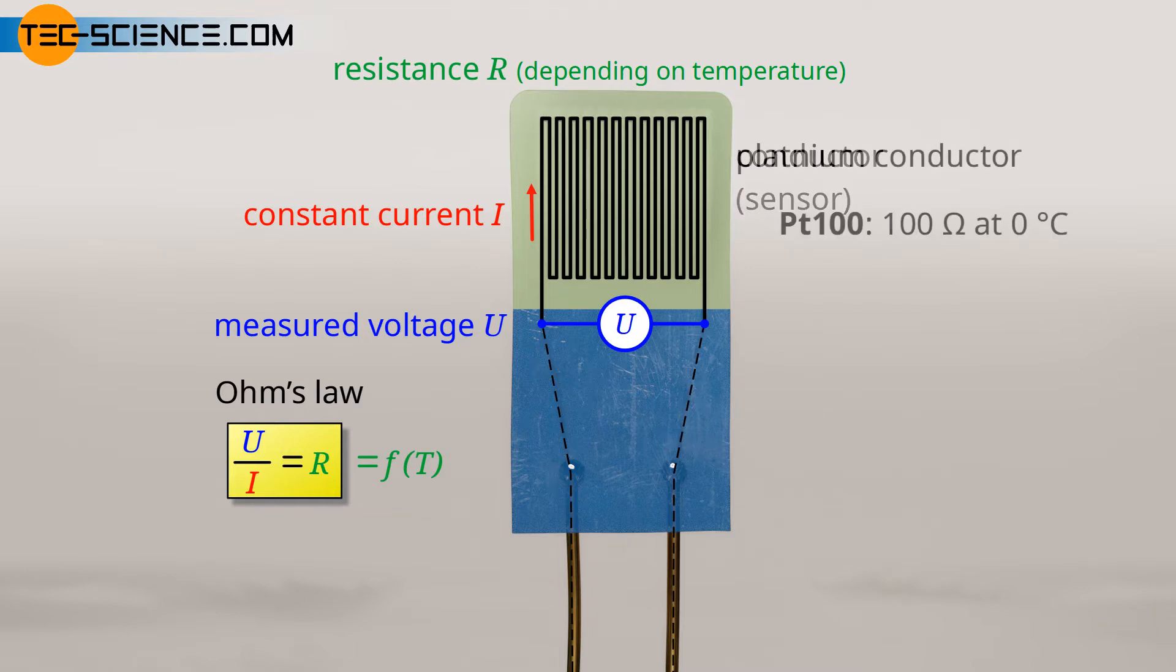A non-corrosive platinum conductor with a nominal resistance of 100 Ohm at a temperature of 0 degrees Celsius is often used as the sensing resistor. These characteristics give this type of resistance thermometer the name PT100. There are also platinum temperature sensors which have a nominal resistance of 500 Ohm or 1000 Ohm at 0 degrees Celsius. These sensors are referred to as PT500 and PT1000 respectively.